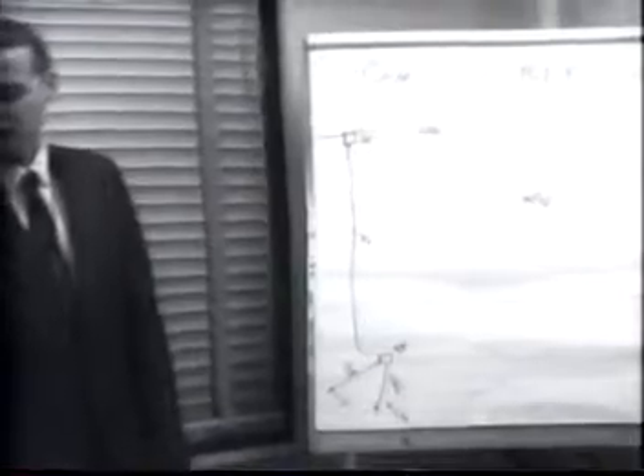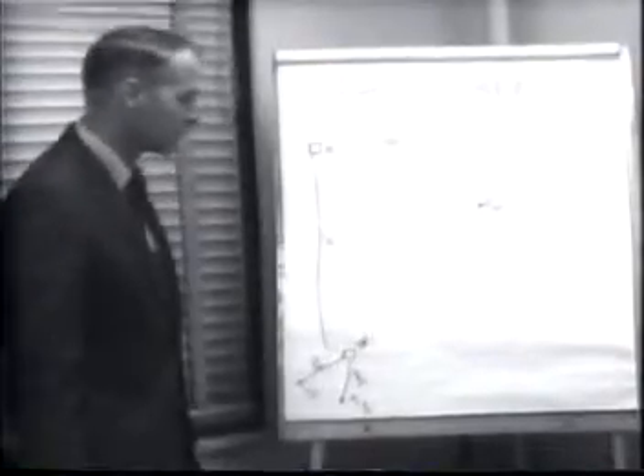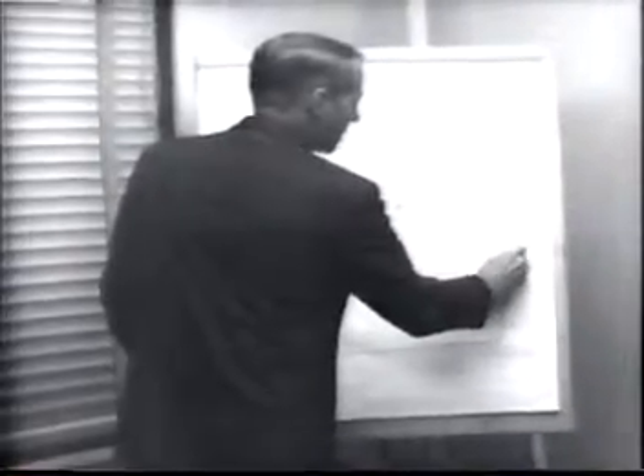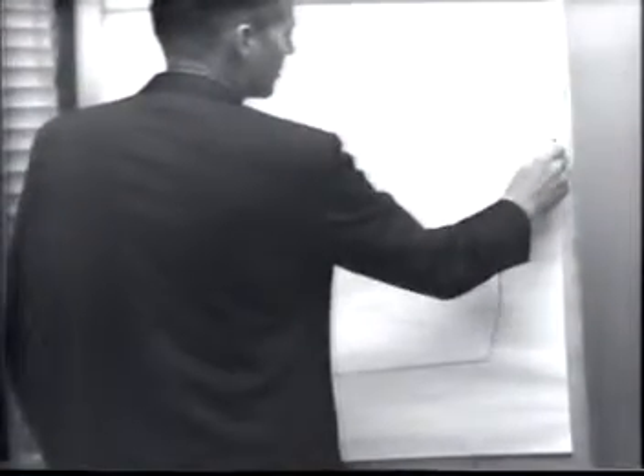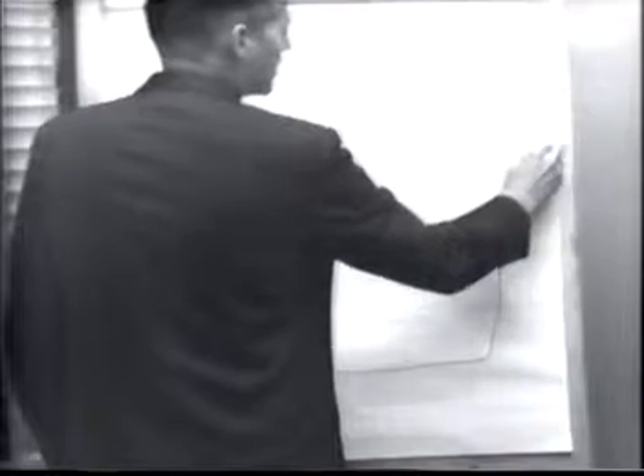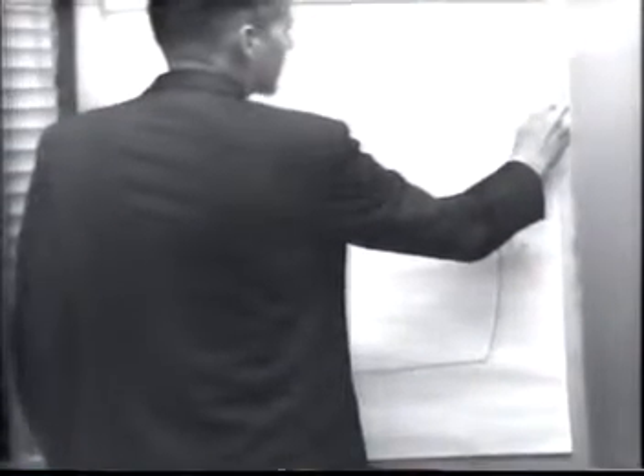point in northwest Davenport where a switching station was called sub 56, which has since become a major transmission substation. And this was put in service at the end of 1960, the first part of 1961. So we can see the beginning of a loop system development here. The next stage in this loop system was the building of a transmission line from sub 18 around to a substation near Barstow called sub 39, and then extending through this substation site to a substation further up river near Cordova, sub 17, and from here then we interconnect with Interstate Power.